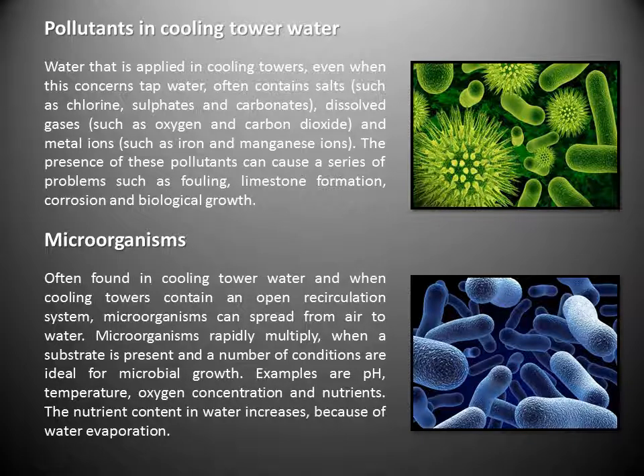Pollutants in cooling tower water. Water that is applied in cooling towers, even when this concerns tap water, often contains salts, dissolved gases, chemical elements, and metal. The presence of these pollutants can cause fouling, scale deposition, corrosion, and biological growth.